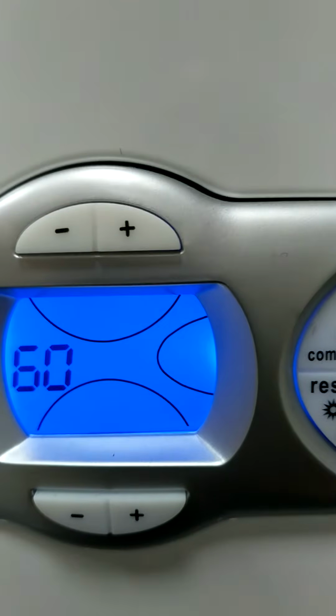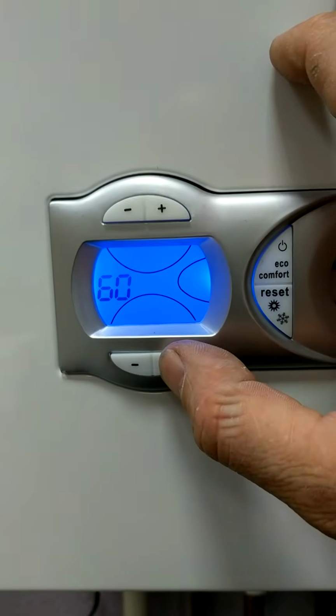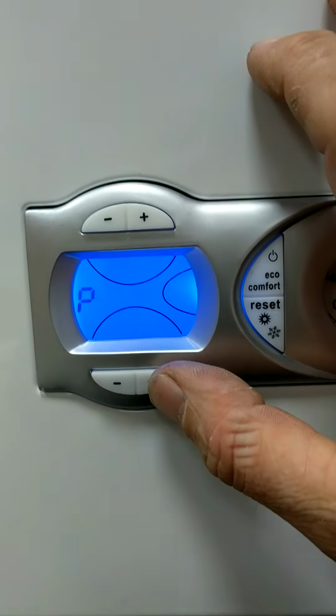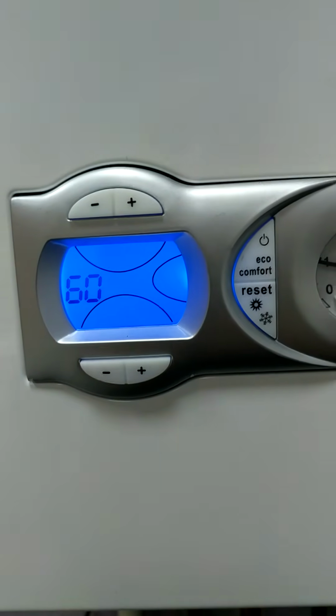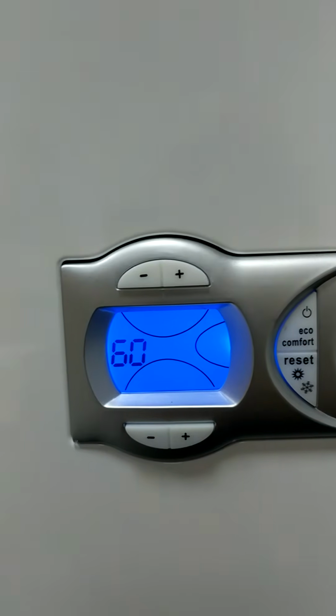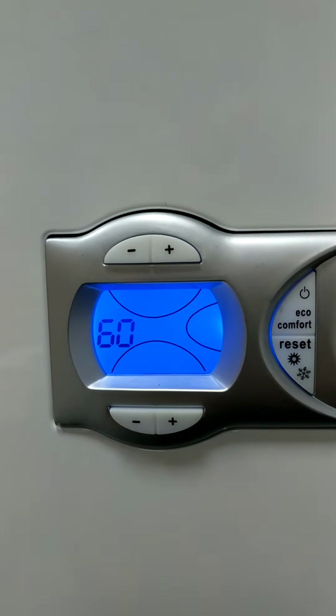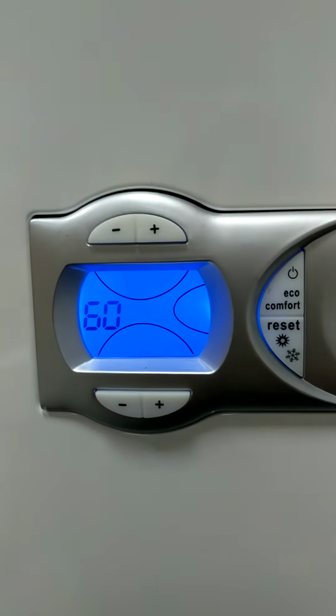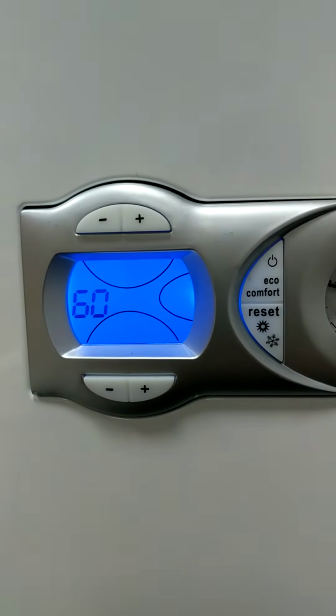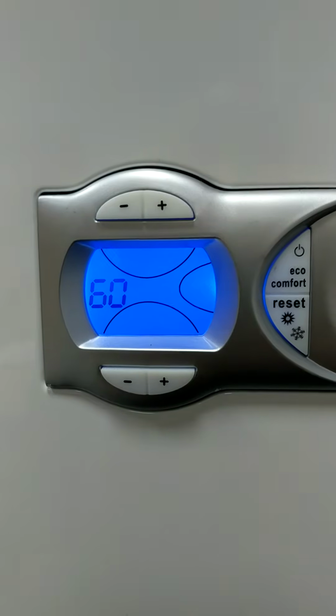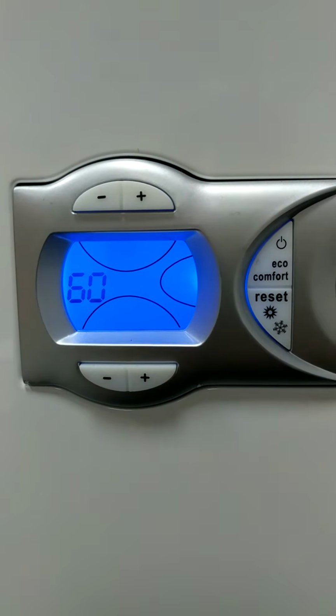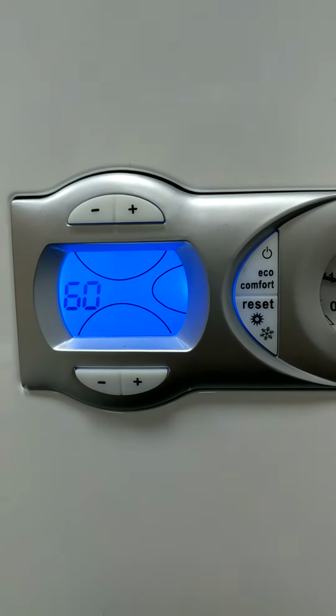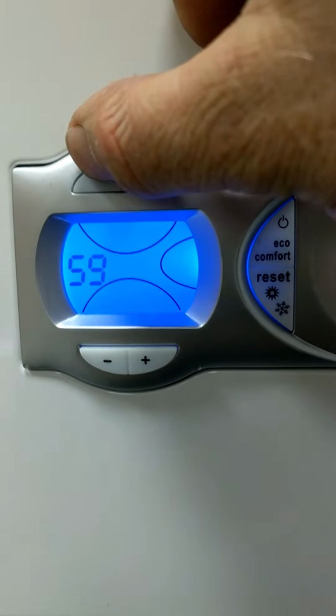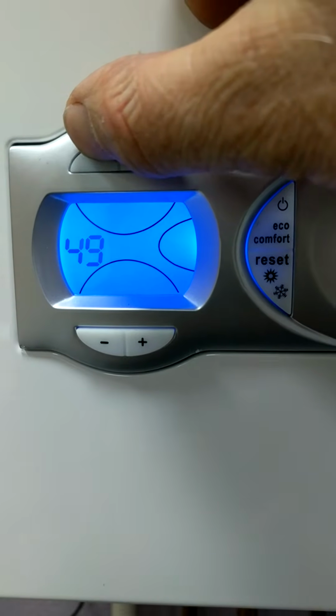So the next parameter we're going to go to is parameter 8, and then the top plus button to see its value. This is the actual hot water delay time. This is how quick you want the hot water delay after the central heating's been on. So if you've got the central heating on, you put the hot water tap on, it normally takes up to about a minute, 2 minutes to come back on, but we're going to knock this down to 10 seconds. So within 10 seconds, the boiler will actually come back on for its heating.